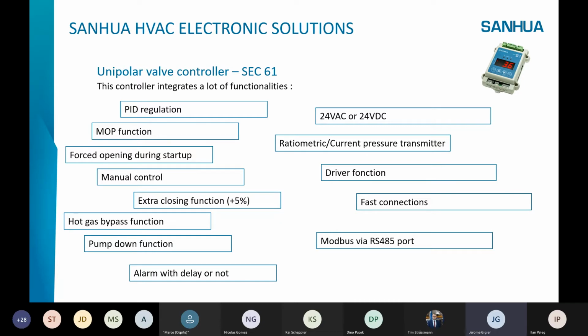You can control, you can open the valve at 50%, for example, to start the test. We have an extra closing function, so it's to be sure that the valve is completely closed. When the controller pushes the valve closed, we have an extra closing to reinitialize the valve. We have also a hot gas bypass function, pump down function. It's more used for refrigeration, but we have this function inside the controller.